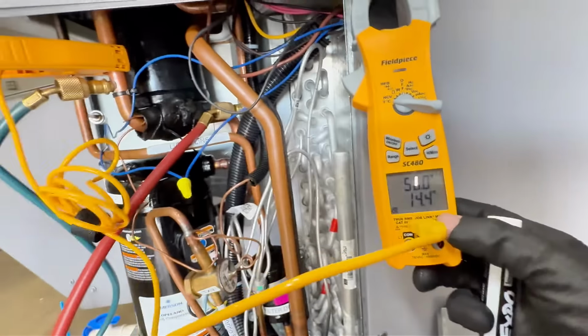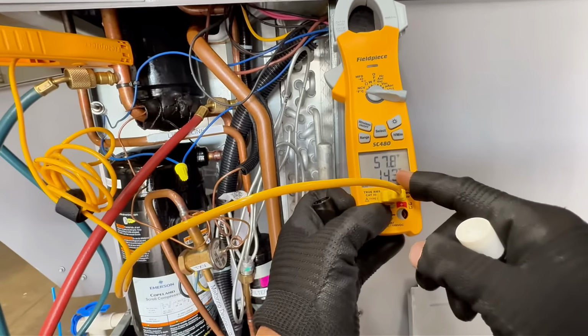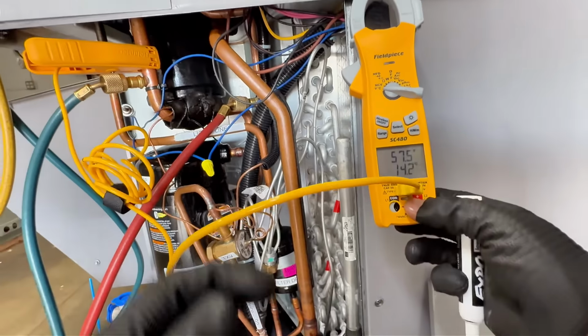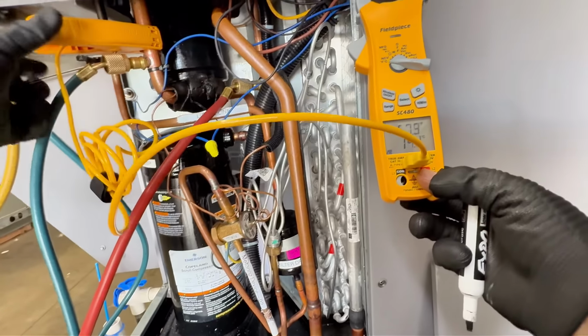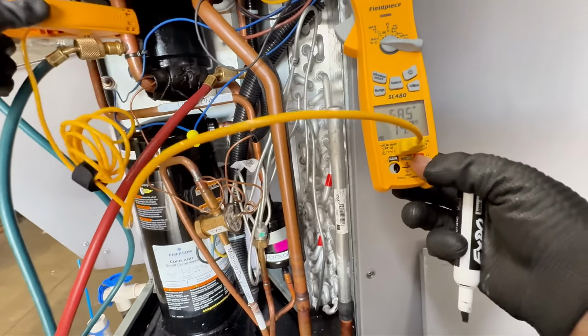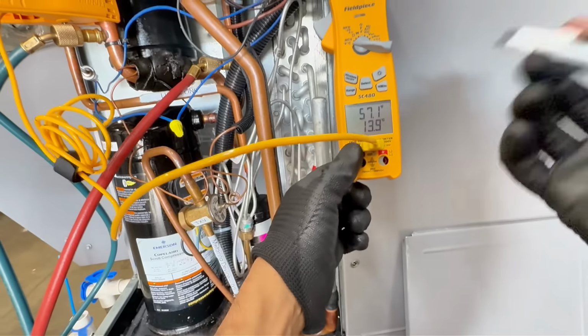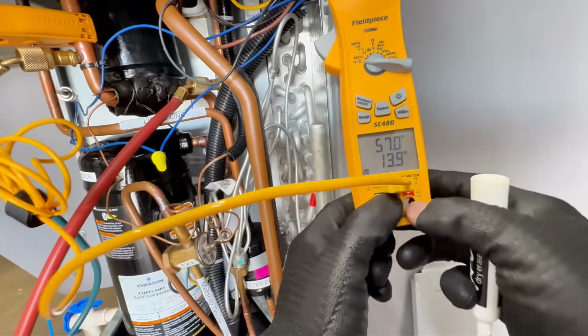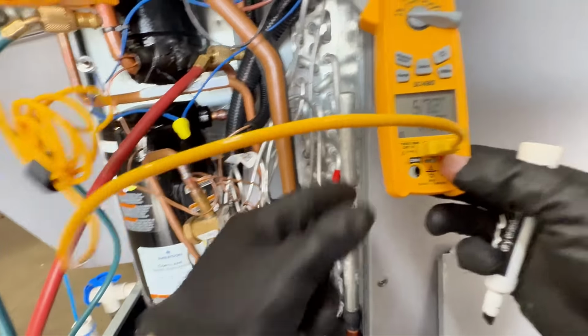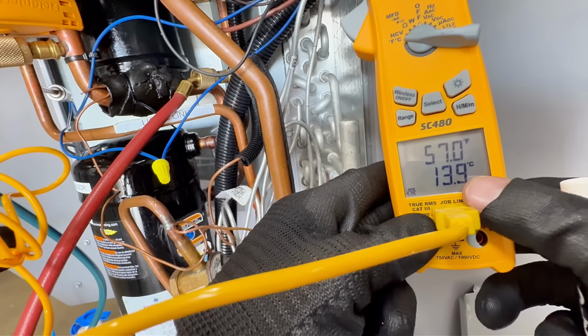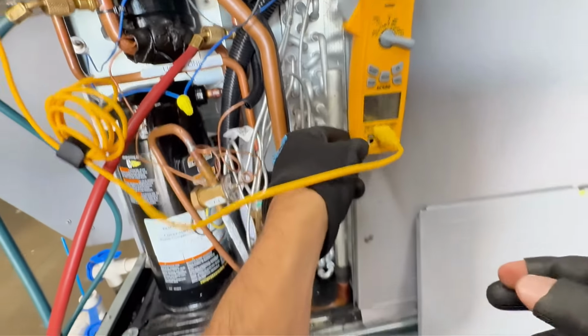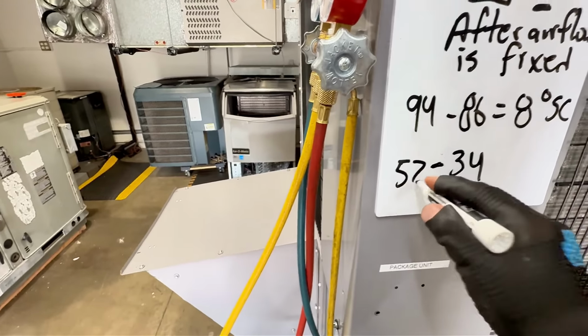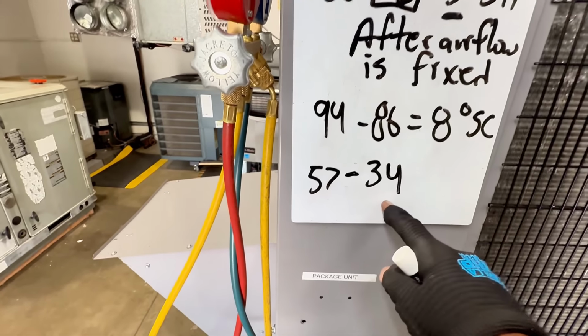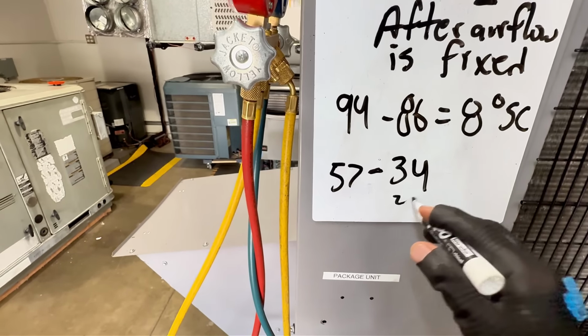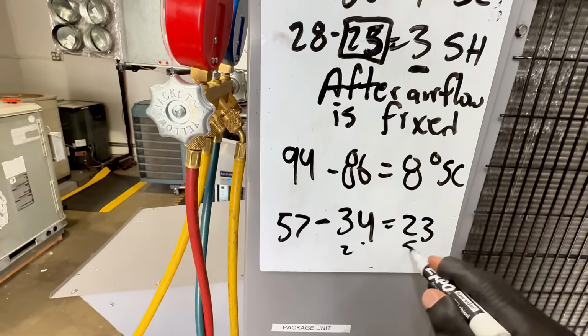One little pro tip here. If you're using digital gauges, you do have to calibrate the temperature clamps, but get a good brand temperature clamp, because sometimes they could be off and it'll throw you off. So just be mindful of that. So let's see where we're at. Right now we are at 57, right? It's not changing, so yep, it's going to be 57. So let's put 57 here. 57 minus 34, what is that? I'm bad at math right now. Is that 23? 23 superheat.